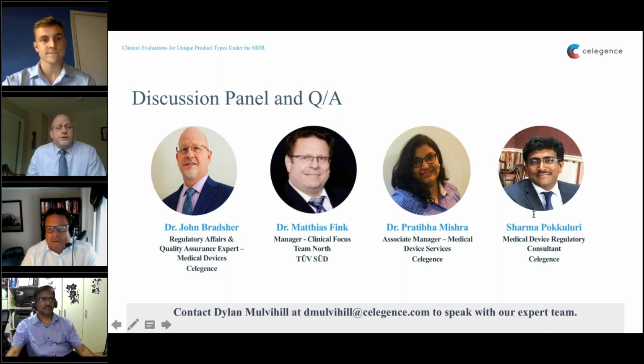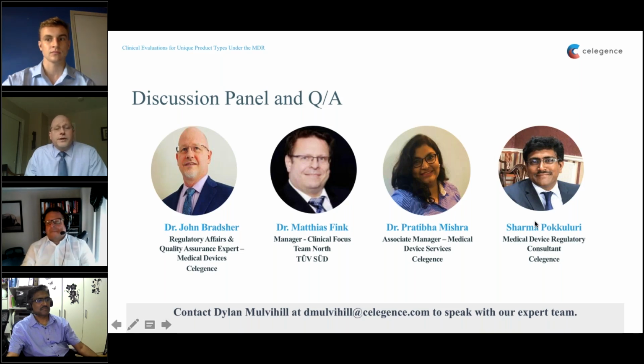Yes, I totally agree. Just emphasizing those points, I'd also add that the requirement from the GSPRs is for risk to be reduced as far as possible. So look closely at your risk management and your PMCF activities to determine if you have a PMCF plan that is going to justify and detail an approach, or provide a justification for why it's not necessary. It will bear a lot of influence from your state of the art, because this is increasingly compared to that of your competitors. So you should be aware of what your competition is doing as well. In addition to those things, use your guidance documents.